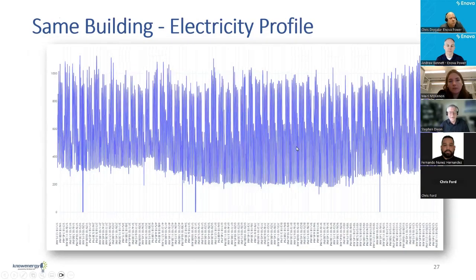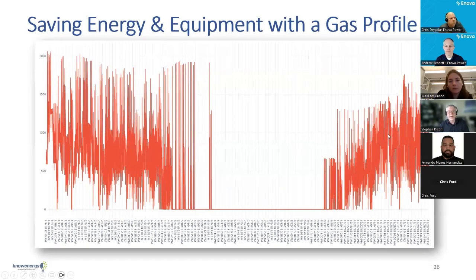In the latter part of the year, they were able to get things under control. You can see more staging of those boilers, 1, 2, 3, and maybe not even 4 boilers. But here in June we've got 4 boilers all on, all off, maybe 3 boilers on and off. That's a big problem. It was funny because the folks in the building were kind of aware the boilers weren't functioning as they should, but they didn't really understand the magnitude of the problem. By looking at the hourly gas data, we were able to figure that out pretty quickly.